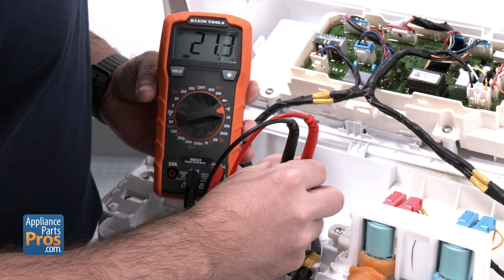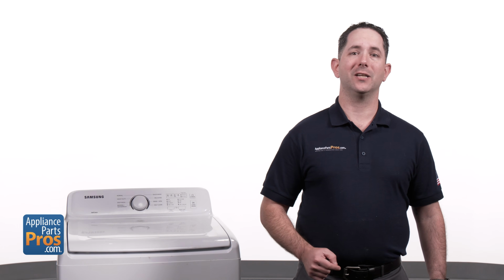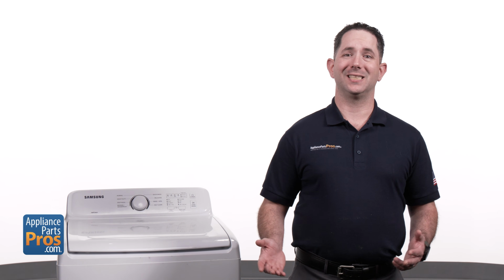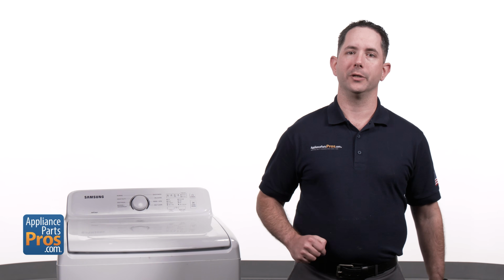If the reading is not close to 21 ohms, the pressure sensor has failed and should be replaced. If the resistance is close to 21 ohms, continue troubleshooting.